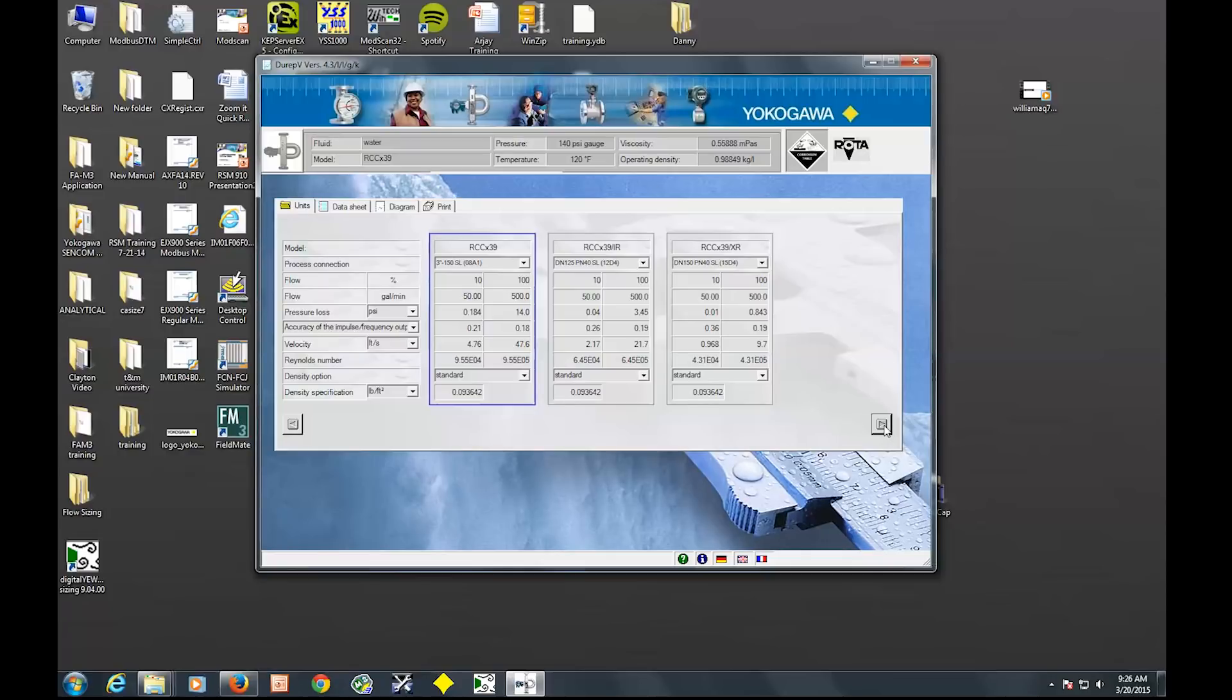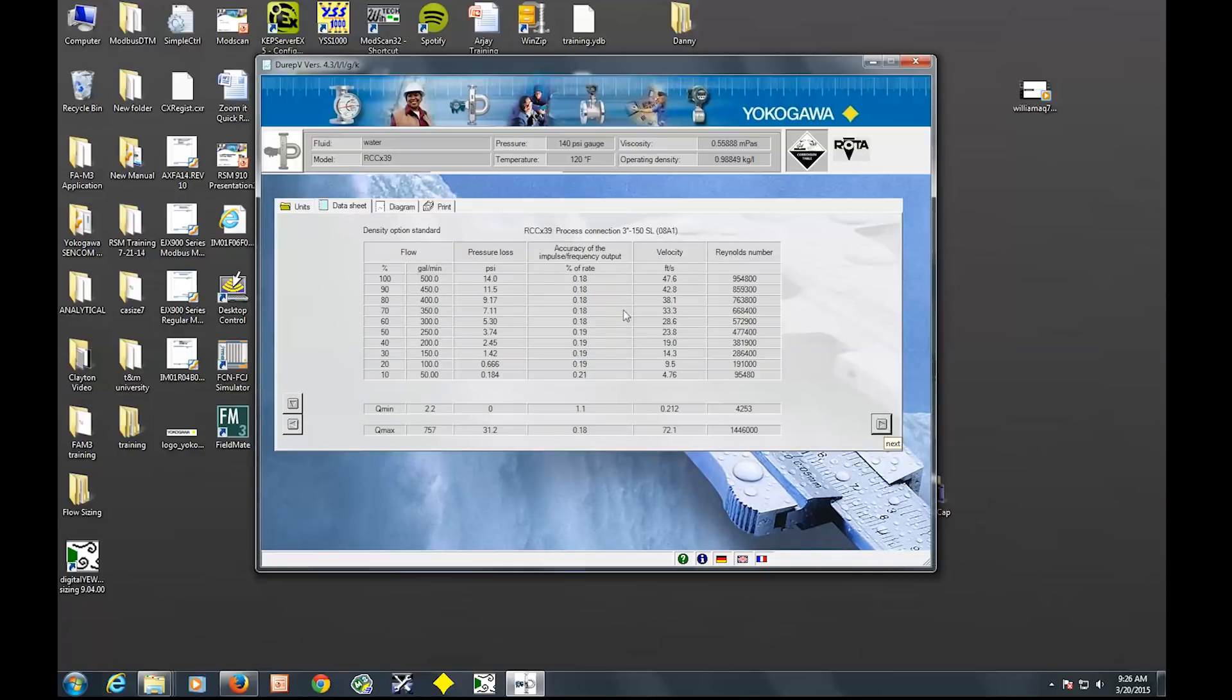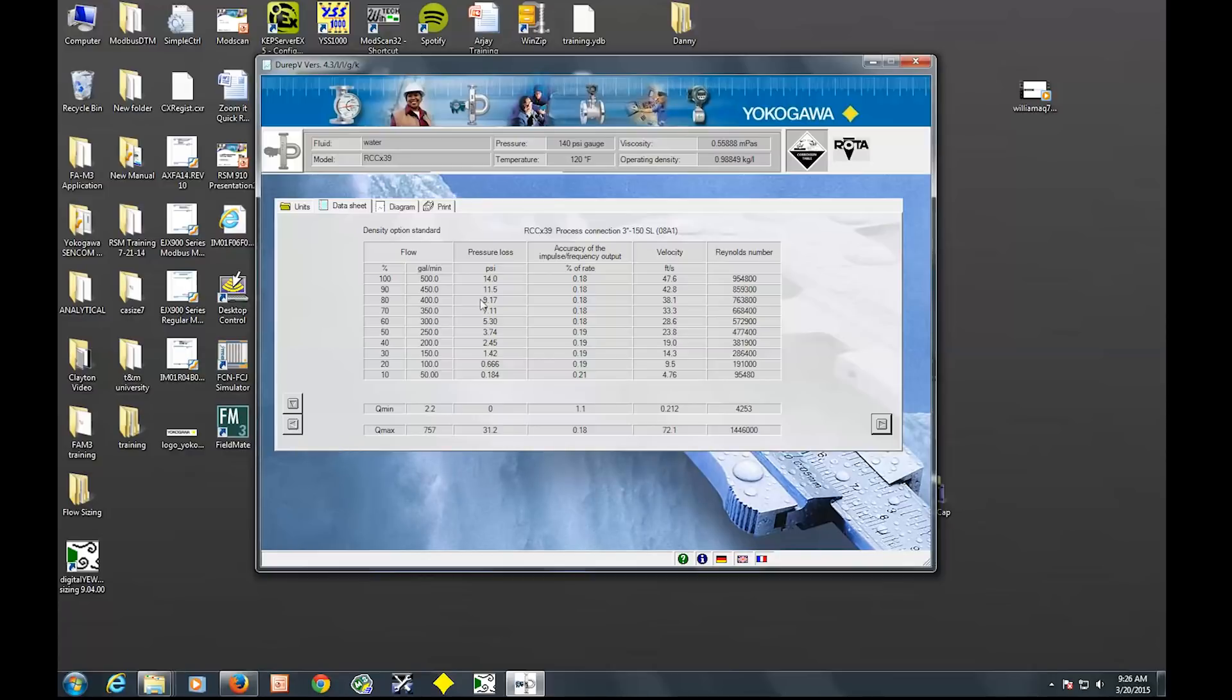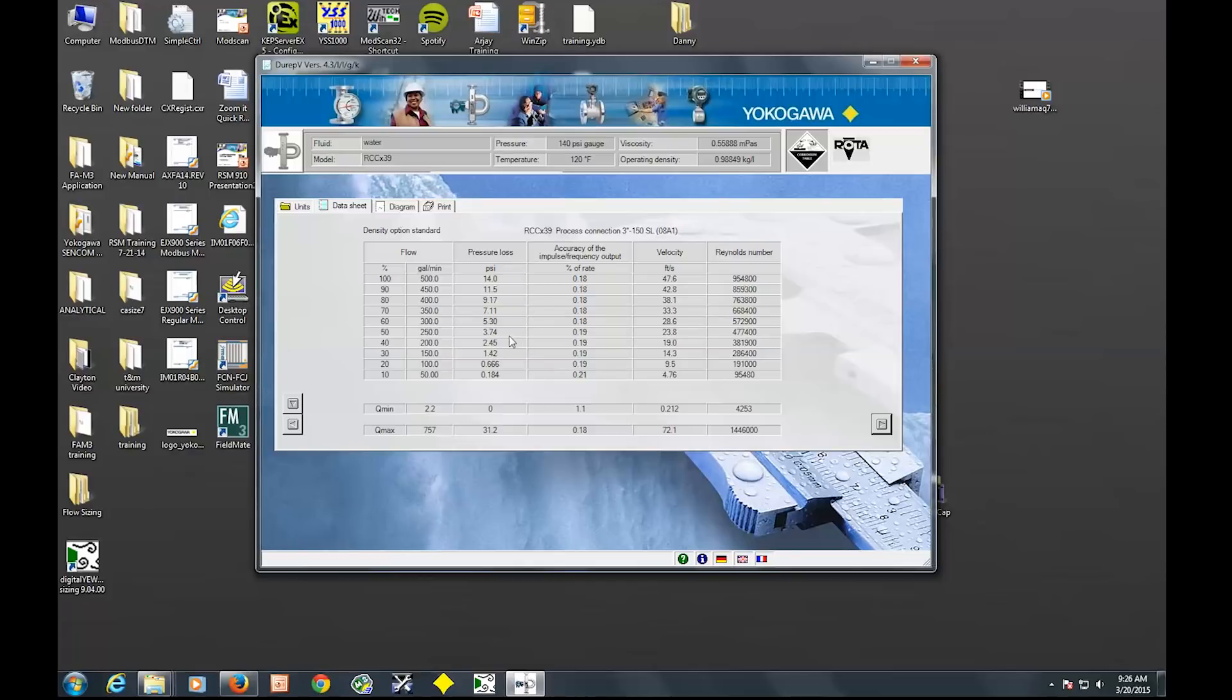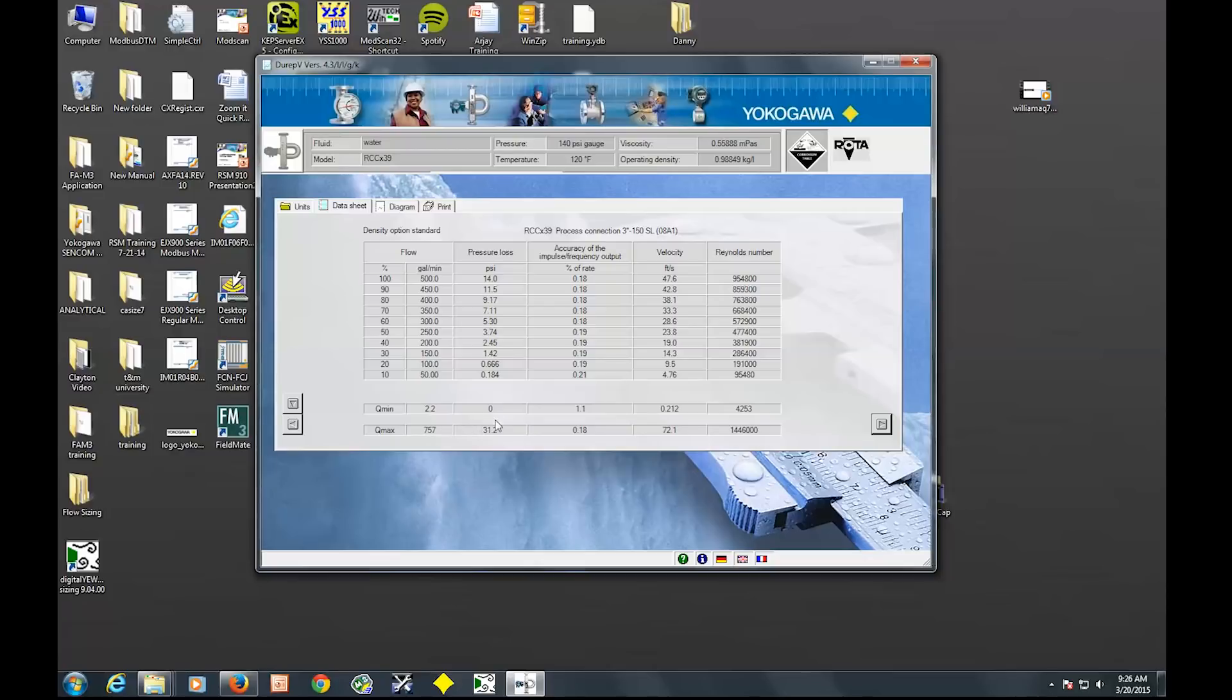So we'll click next. It's going in this order, so if you need to go back and change something for whatever reason, you can go back. So this is the sizing basically for the range specified, or the Q max specified. It gives you your pressure loss at each value, or each flow rate, then the accuracy you can expect, and the velocity through the meter, as well as the Reynolds number. And then at your min and max that the meter can handle, the same thing: pressure loss, accuracy, and velocity at the min and max.